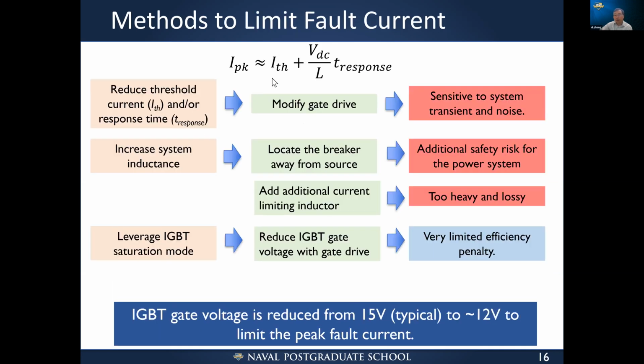So I mentioned the peak current can also affect the solid-state circuit breaker's performance, right? So if we want to reduce the peak current, the first thing we can do is reduce the threshold current. One way we can do that is to modify the gate drivers, to make sure that the gate driver can kick in and detect faults earlier, and we can also reduce response time. However, both of them will make it sensitive to system fault current, but at the same time, it's also sensitive to system transients and noise, right? If we really push it, reducing margins, this can falsely trigger the breakers in normal operation.